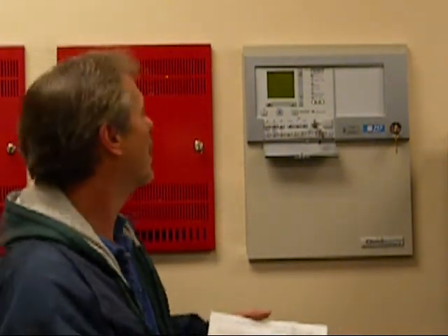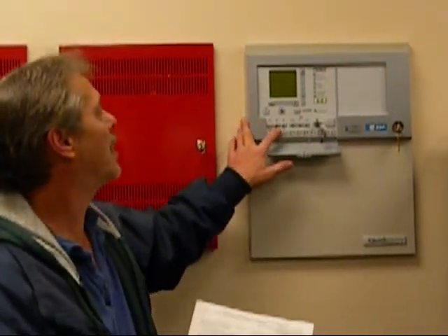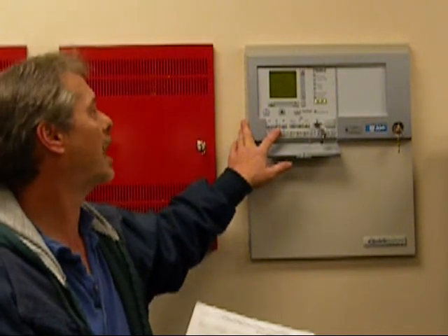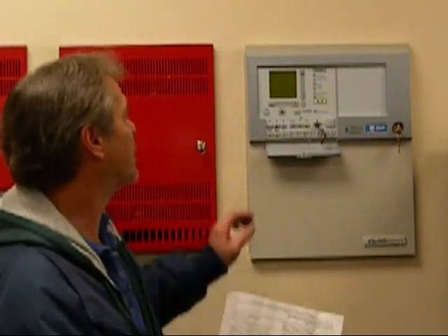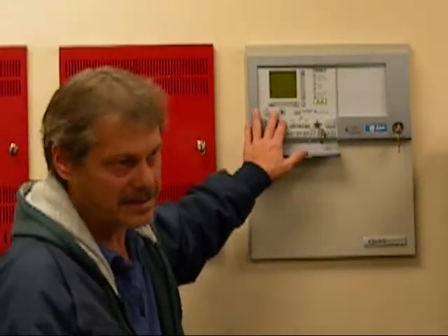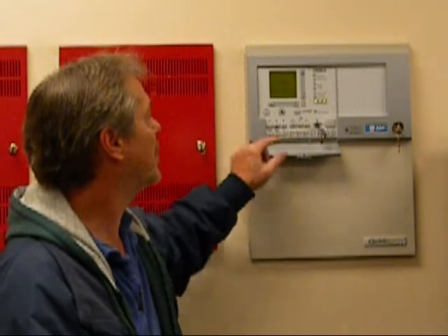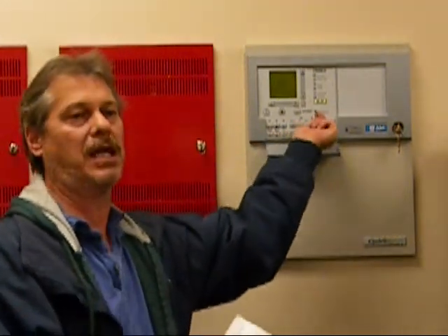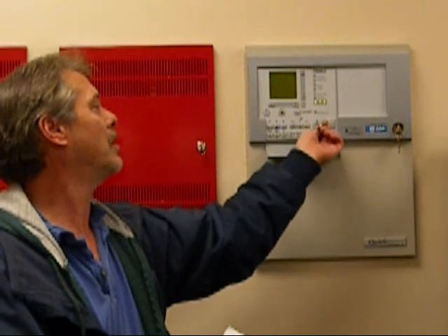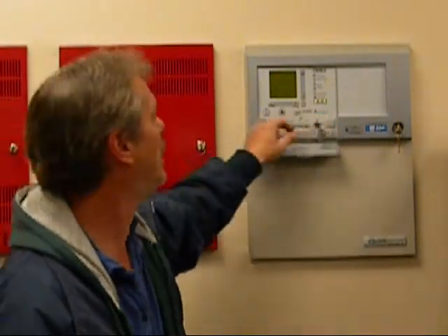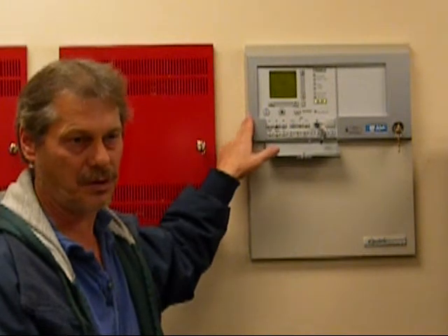Okay, if the fire alarm occurs, once you have authorization and once the building's been evacuated and deemed safe by the proper authorities to re-enter the building, you can silence the alarms. That is done by pushing the alarm silence switch. Now, anytime you push any of these buttons on this panel, you need authorization. Besides touching the panel, you need authorization to push the buttons. That authorization is given either with the key, by inserting the key into the front of the display and turning the key to on. That will enable the controls at the main panel.